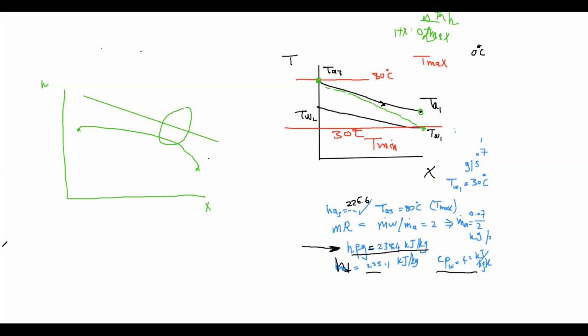But for our case here, as far as we are concerned in this course, we are going to consider the enthalpy the way that we have written before. We consider effectiveness for the dehumidifier at the air side and at the water side, compare between them, and take the highest. The same thing for the humidifier: effectiveness at the air side and at the water side, comparing between them to get the maximum. Basically, we are considering the points at the inlet and exit of the unit, so we have the terminal values. These are the values that we calculate, and we write our value of the effectiveness based on that. This is exactly what we have done in the previous example.